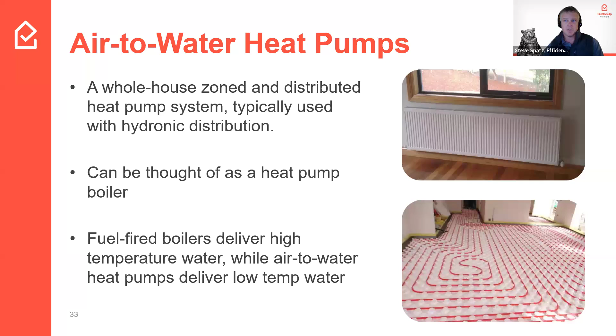Fuel-fired boilers, as Bob had mentioned, are high heat systems, so they're designed to deliver a higher temperature water throughout the distribution system that's going to be in the home, while any type of heat pump equipment is considered low temperature distribution and low temperature energy that is being created here. So there's a limit to the amount of heat energy that can be created with the refrigerant process we have available now. That just means that when you're considering using something like an air-to-water heat pump, you have to have a distribution system in the home that is matched for what the heat pump is able to deliver.